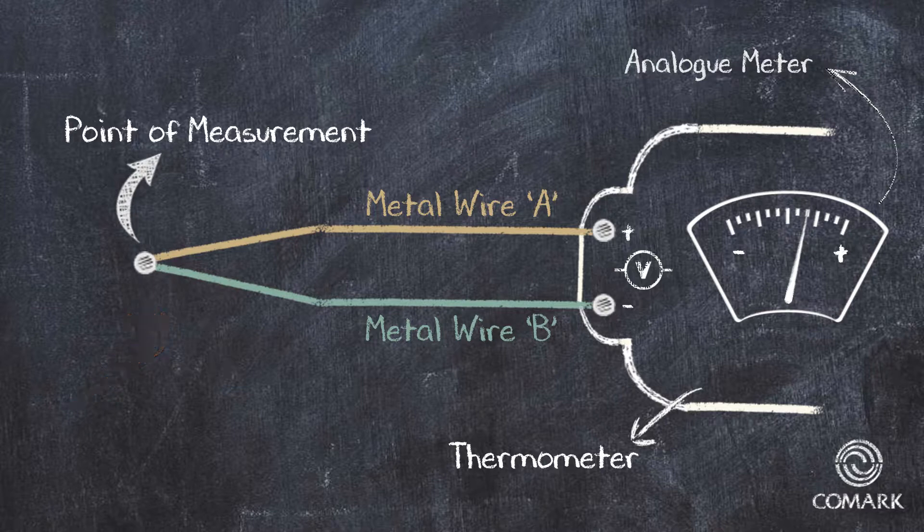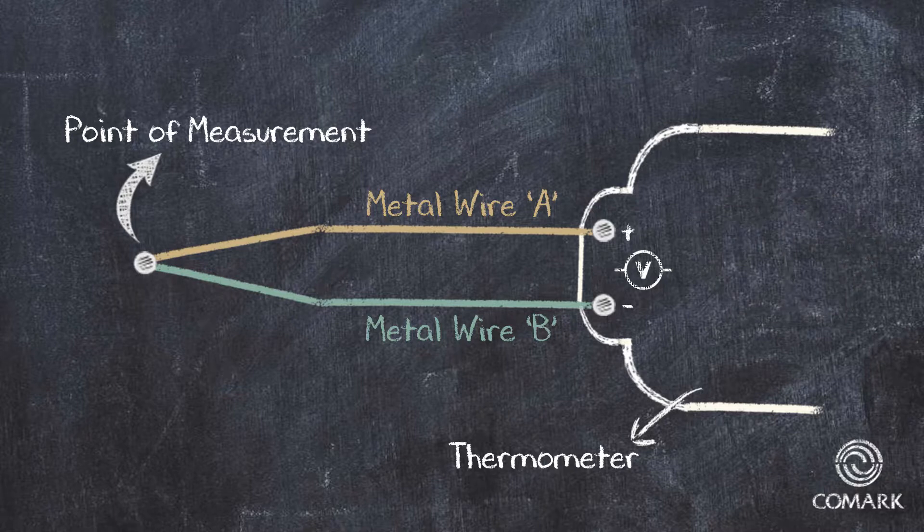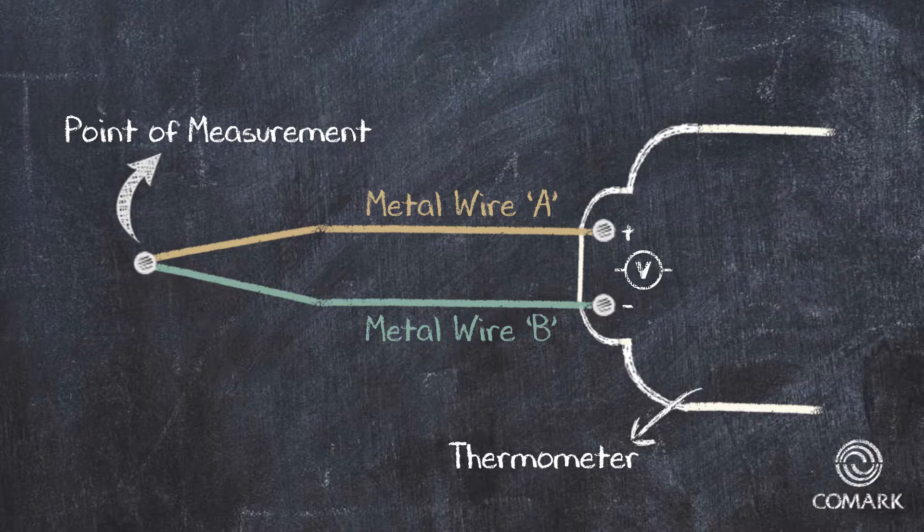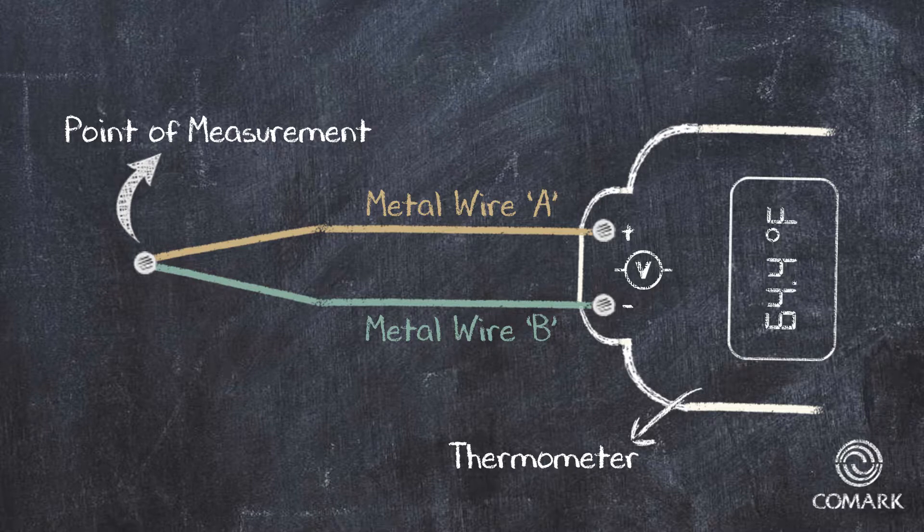The thermometer effectively measures this voltage, performs a quick calculation to correct for ambient temperature, and then uses a lookup table to determine the actual temperature at the point of measurement, which it then displays digitally for us to read.